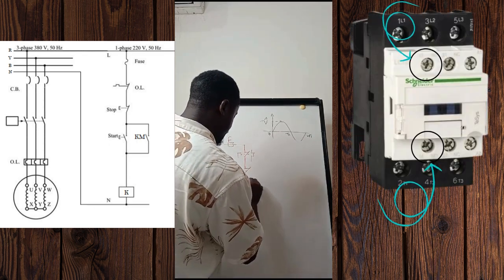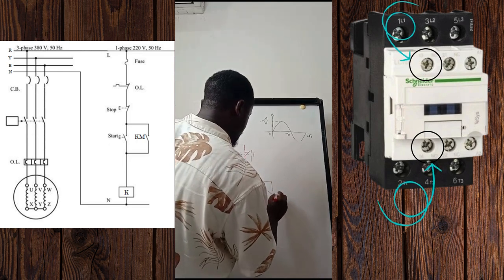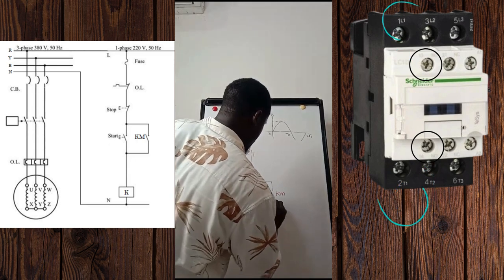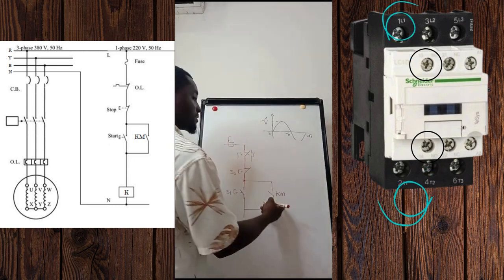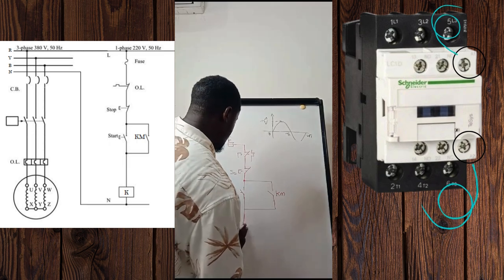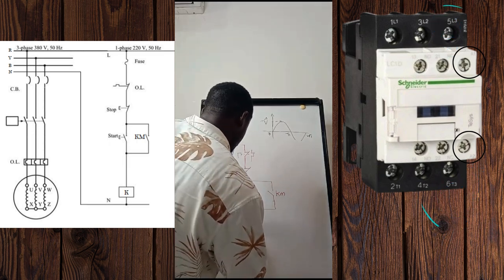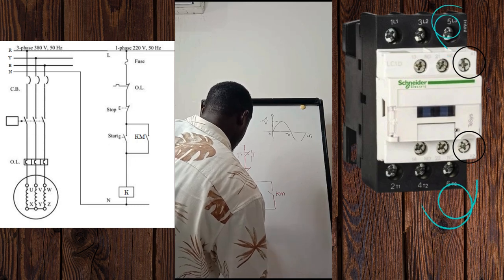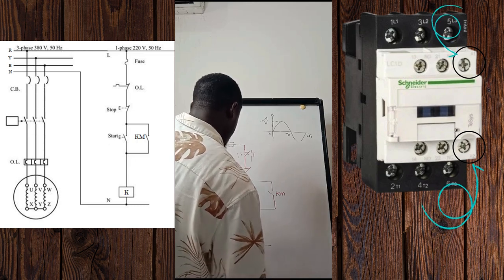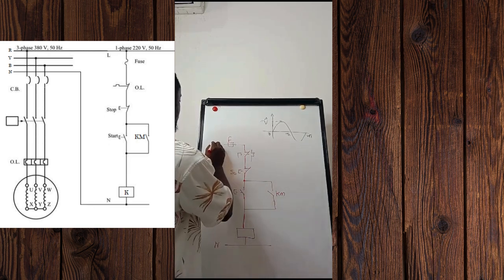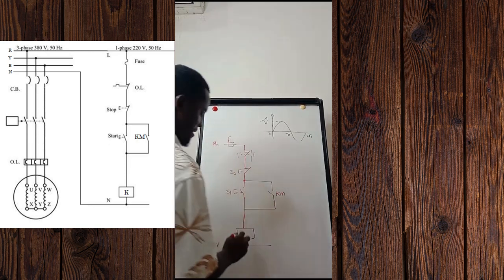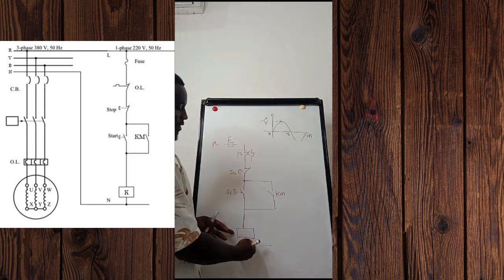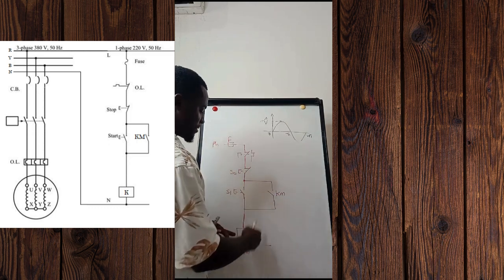Here we have our contactor, which is KM. We connect to the normally open contact of the contactor, which in this case is going to be 13-14 of the contactor. Then we have our coil, connected back to the neutral. This is the phase and this is neutral. So KM is the contactor — this is the coil of the contactor and this is the normally open contact of that same contactor, KM.